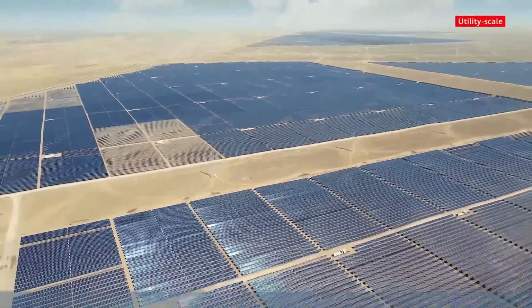Now let's move on to the next section, energy storage. This is the first physical display of Huawei LUNA2000 Smart String ESS. Come on, let's take a look together. Smart String ESS is a standard 20-foot container with rated capacity of 2,064 kWh, a very high power density. As we can see, 6 battery racks are connected in parallel. Each rack has 21 battery packs in series. Each battery pack is 16.384 kWh.